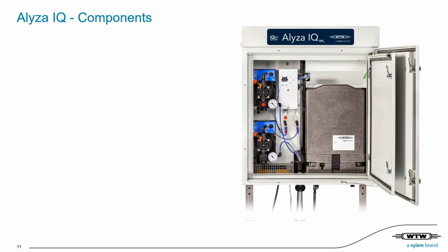So with that, let's review some of the main components of the new analyzer in the direction of the sample flow at the two-channel version. Here you can see the two filtration pumps with individual pressure sensors. The results of these sensors can be used to check if a cleaning of the filter is required or if the sample tubing might be clogged. Here you can see the two overflow vessels, which are made out of transparent material, so you can visually inspect it for any solids buildup.